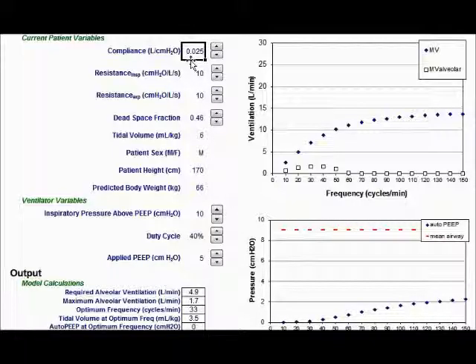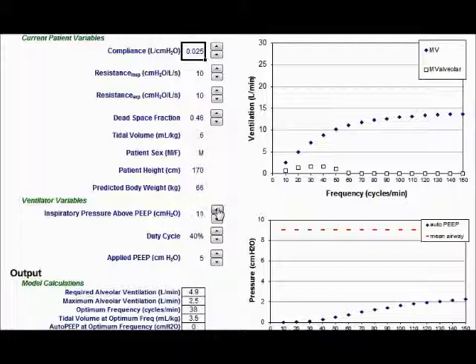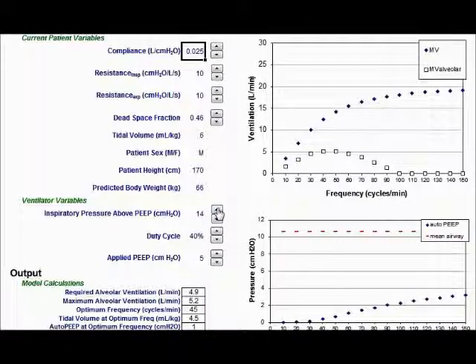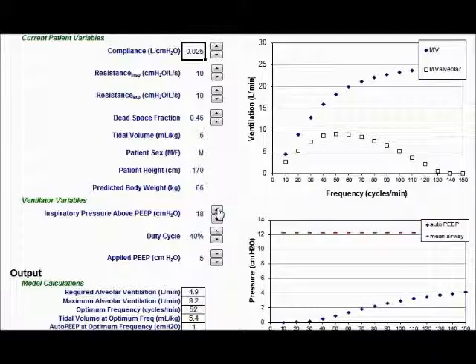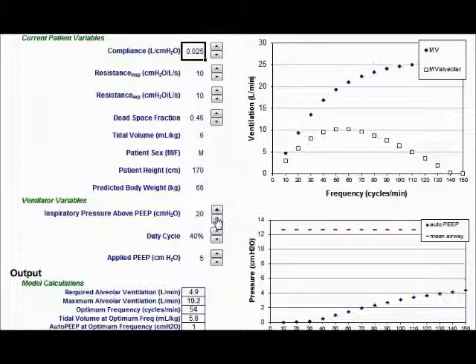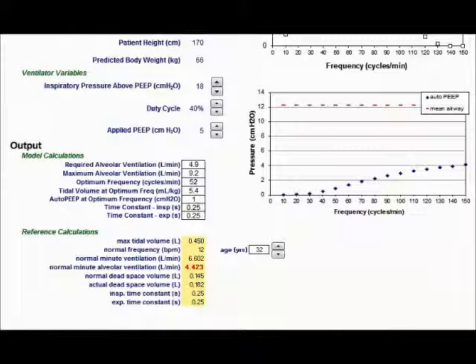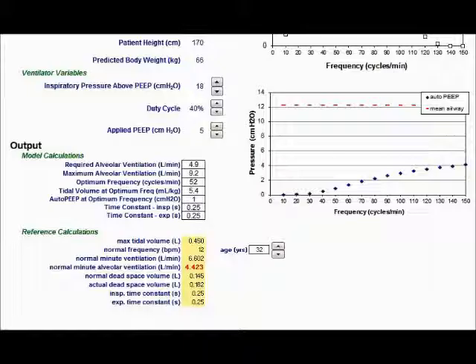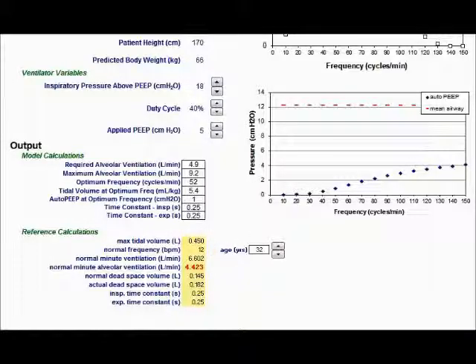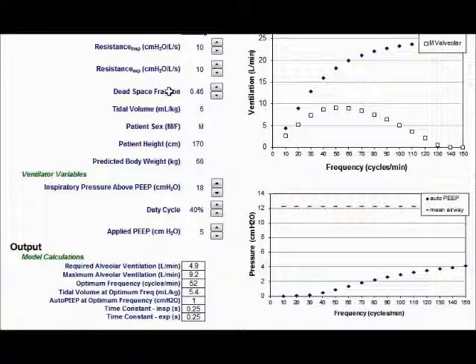So let's go ahead and try that. I'm going to go up by 8 centimeters of water to a pressure control of 18. And now my max tidal volume that I can generate is 450. Like I said earlier, we can now target tidal volume — we can predict what the tidal volume is going to be based on looking at compliance and using the pressure control setting.